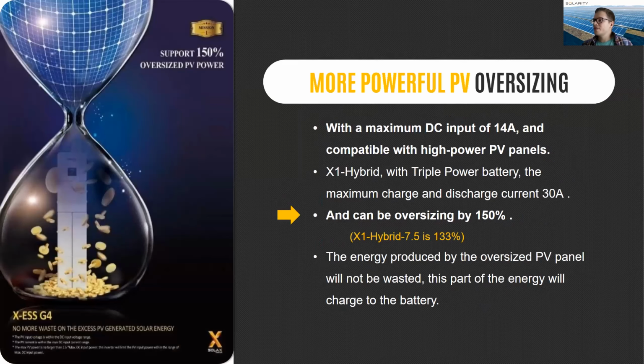Of course, you can oversize the system. For a three-phase system, it can be oversized to 150%. For the single-phase solution, it can be oversized to 133%. The maximum DC input current is 14 amperes, and the maximum discharge current is 30 amperes. People usually like to oversize the system, right?